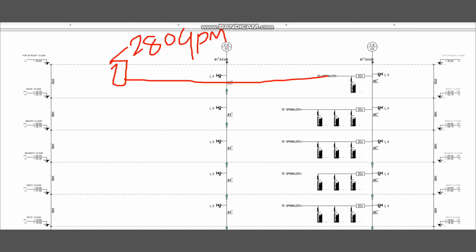So in the third scenario, as I told you, sprinkler plus fire hose cabinet we need to consider. For example, sprinkler flow is 280 GPM. So this is the remotest location. The pipe is coming like this, and which is going all the way down till the fire pump. So in this case, I need to add this fire hose cabinet flow. That means I told you one fire hose cabinet 50 GPM I need to add.